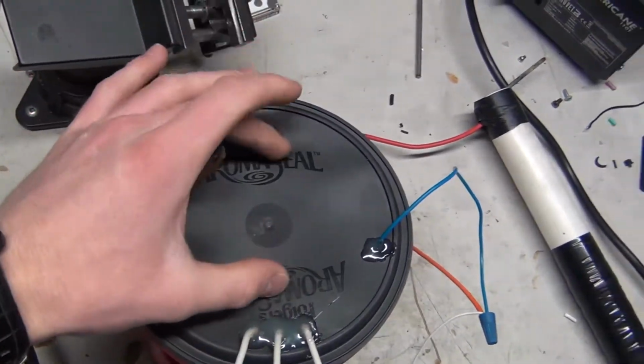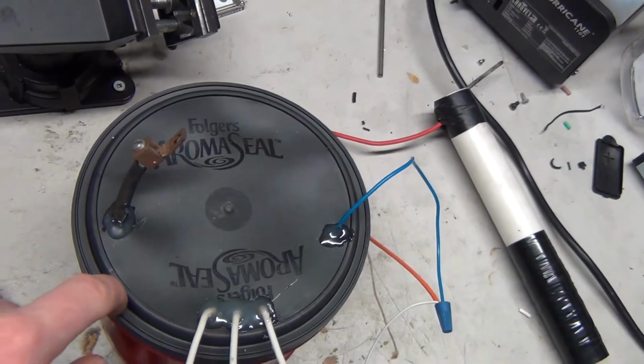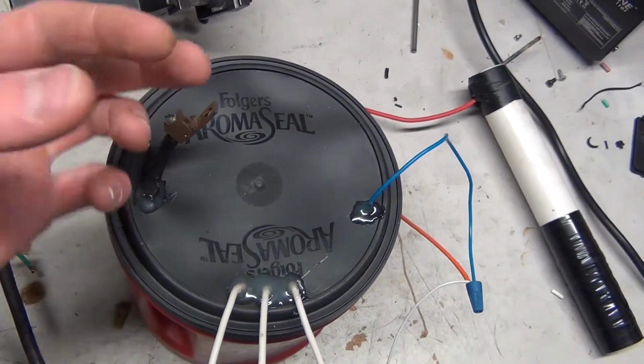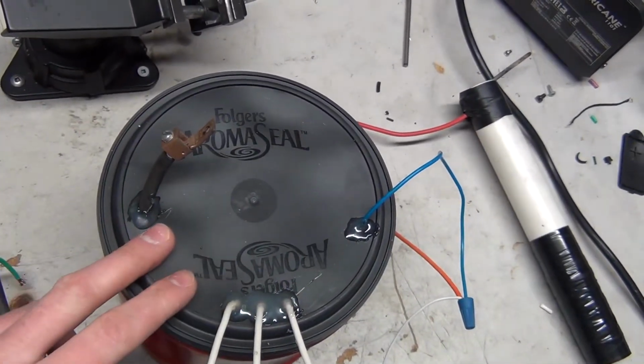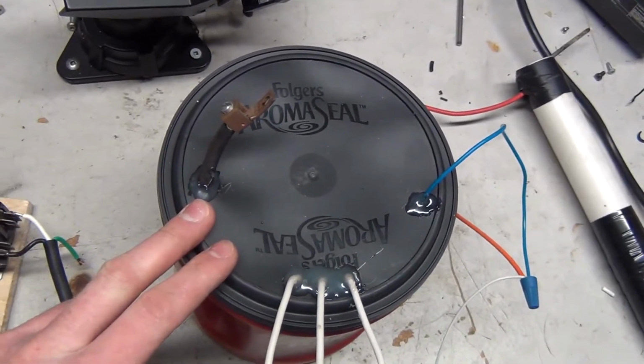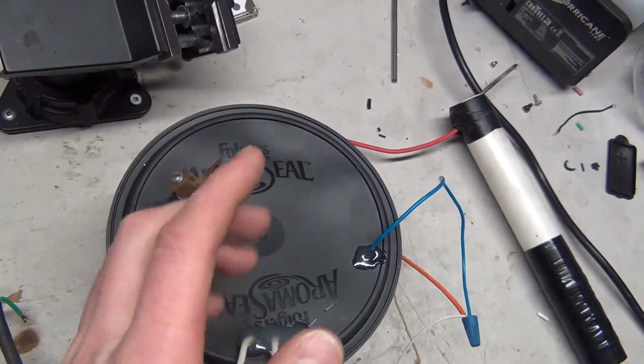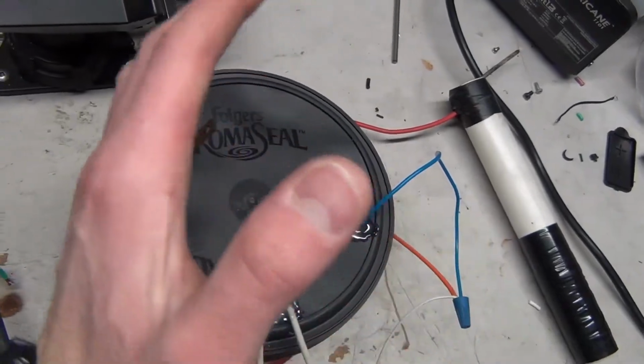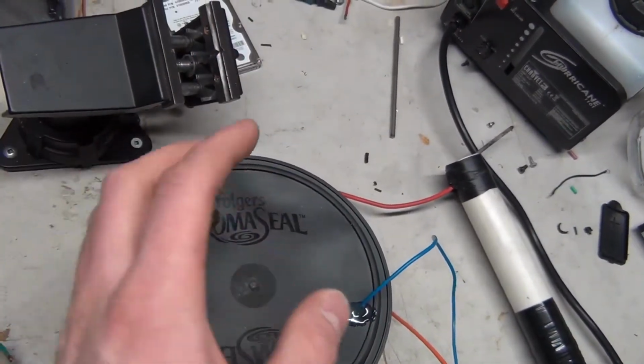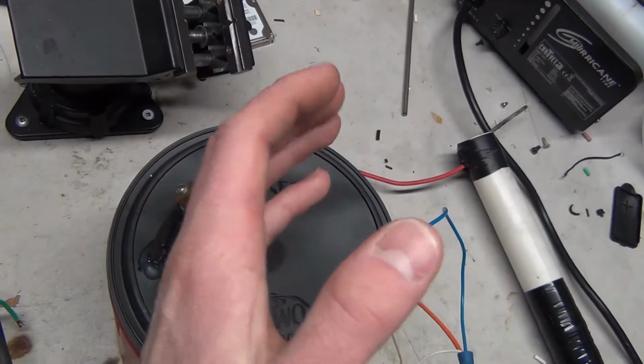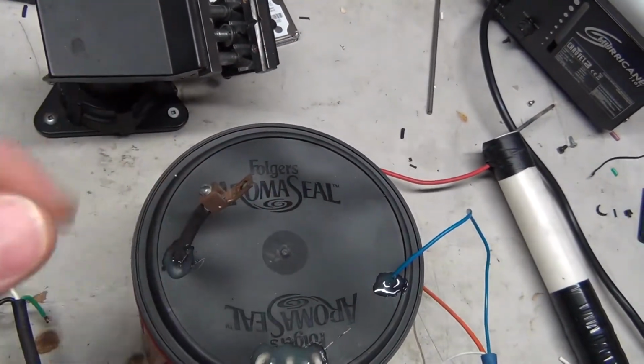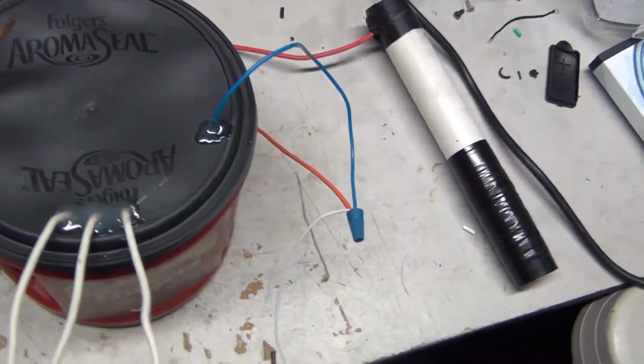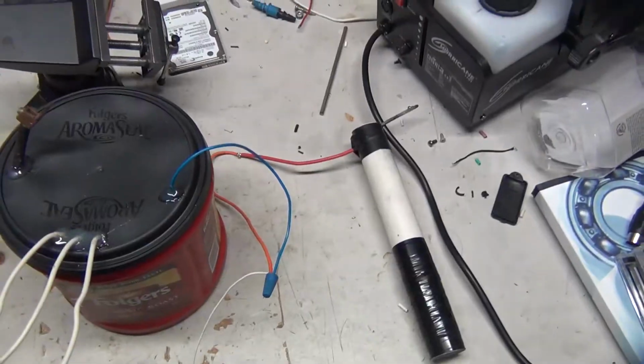It was an issue not with my transformer design and construction, but just the overall winding itself. My last couple turns on the secondary there, I left some slack for some reason. I don't know, I just must have forgot about it, but the slack had the wire bending out. It wasn't wrapped tightly around the bobbin, so it bent out and hit the side of the iron core, which is grounded to earth here.